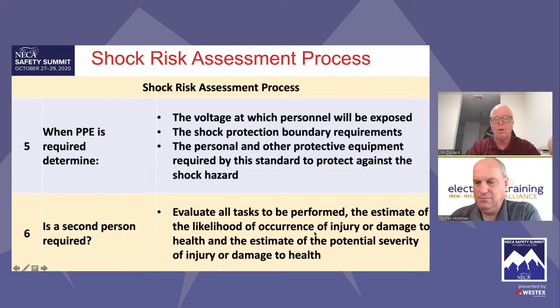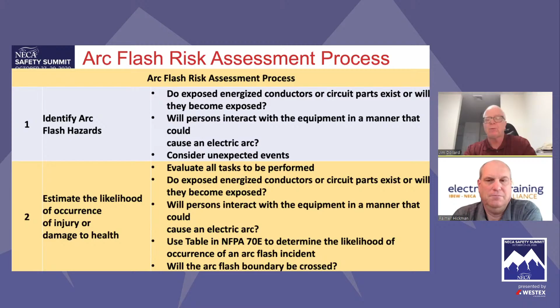Very similarly, Jim, arc flash risk assessment process: are there exposed conductors or circuit parts? If there are, I've got an arc flash hazard. Are we going to interact with the equipment in a manner that increases the likelihood? If that's true, then I have an arc flash hazard. Then I estimate the likelihood. I've got to take a look at the tasks. If I have exposed conductors or circuit parts, if we're going to interact, we can use Table 130.5(C) to determine the likelihood. Are we going to cross the arc flash boundary?